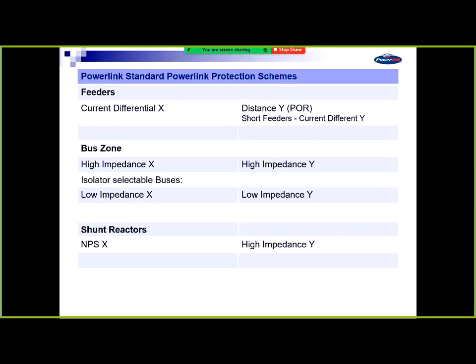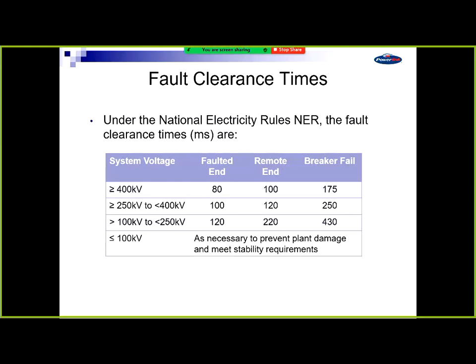The bus zone is usually high impedance, X and Y. And for isolator selectable buses, we have a low impedance scheme. Do you want me to grab that one? I'll grab that one. And shunt reactors, we have negative phase sequence and high impedance. Most of our shunt reactors are on the feeder, so they're also inside the feeder protection as well.